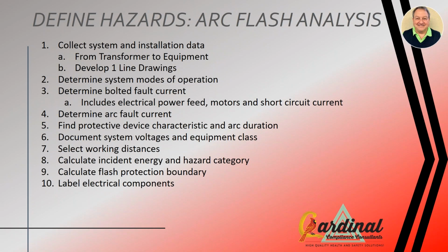And from there, we develop what the arc current would be. Obviously, there is some resistance through the air, and we're learning more about arc flash all the time. We're finding out geometries of the bus bars, spacing of the bus bars has an influence on the level of fault current, arc fault current that is. So from there, we take a look at what the devices are in terms of fuses and breakers for interrupting a short circuit. How long does it take for them to open and clear the short?